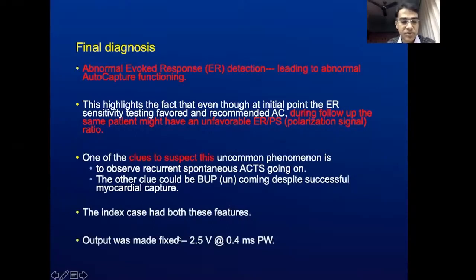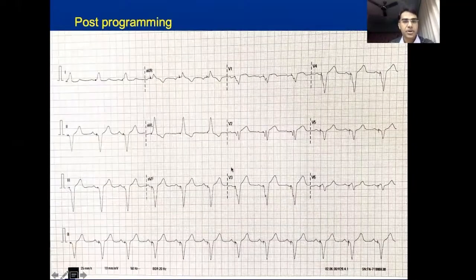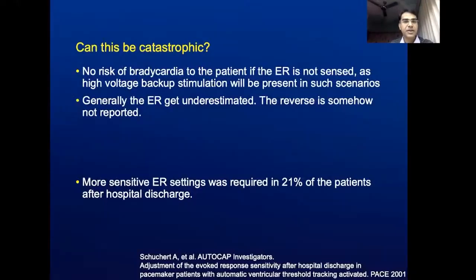What we did for him was, since his threshold was stable at 1 volt, we made it 2.5 volt at 0.4 pulse width, and we observed him for the next 15 minutes. In fact, he has been coming for follow-up over the last 6 months, and there is no such ECG recorded on follow-up. This is the post-programming ECG. So the most important question that comes to mind is, if this can sometimes become erroneous, can it be catastrophic? Fortunately, there is no risk of bradycardia, because if the evoked response is not sensed, a high voltage backup pulse or stimulation is going to come anyway.